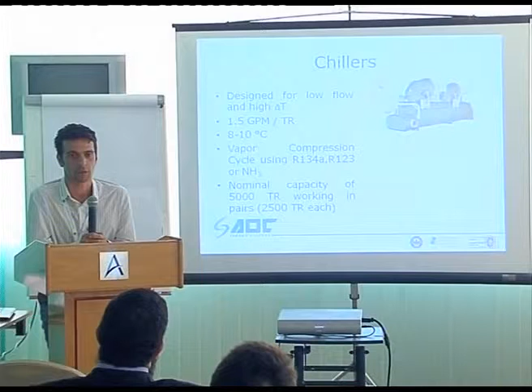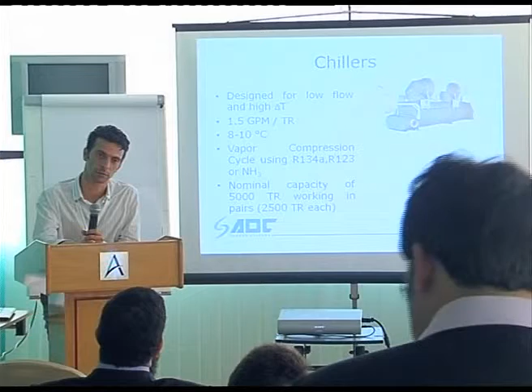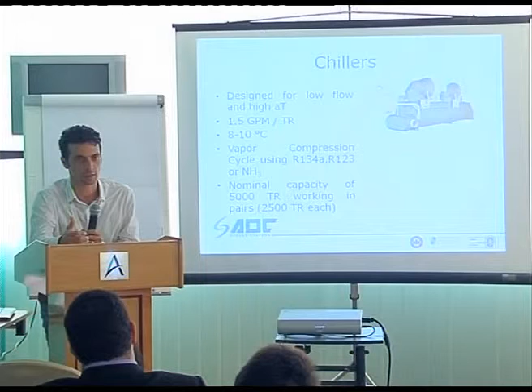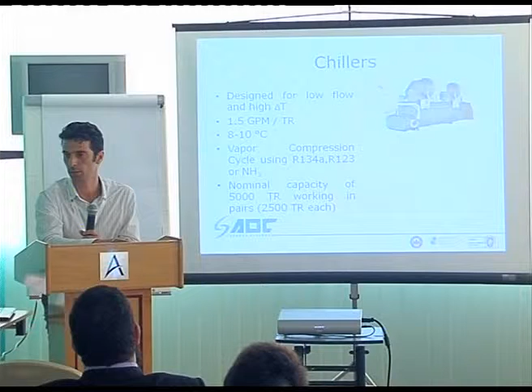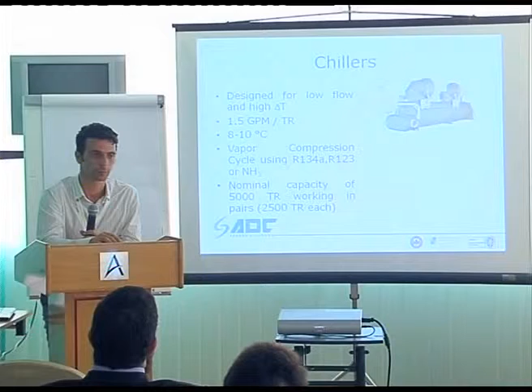Every material is poisonous. Every material can harm you. Even water can harm you if it's used in the wrong way. Ammonia is a poisonous gas. So is 134A. So is R123. Each one of them has a certain degree of dangers that you need to mitigate and limit. But there is no problem in using ammonia. There's no problem in using any other refrigerant. Why I prefer ammonia? Because it's more efficient than any other refrigerant there is. It's fully natural. It's zero ODP. It's zero, what's the other one? Global warming potential, GWP. Okay. I'll talk about ODP only.